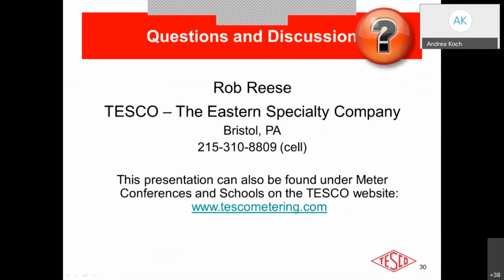Great. We always did a service analysis anytime we changed the meter or there was any alteration to the service whatsoever, or a contractor had been into the switchgear for whatever reason. Other than that, we did exactly what Rob said, which is we had an annual program where we'd go around and test all the CT rated services. But it's just a wise thing to do anytime there's been an alteration to the service of any sort or any maintenance done on it over the Christmas holidays or whatever. Good idea to get in there and retest.